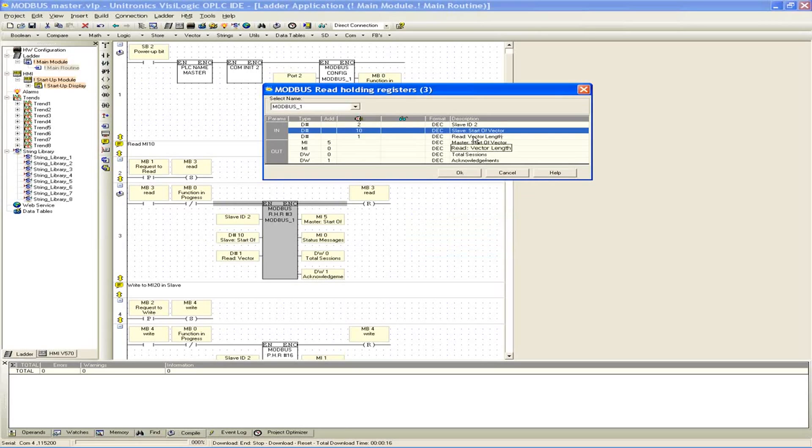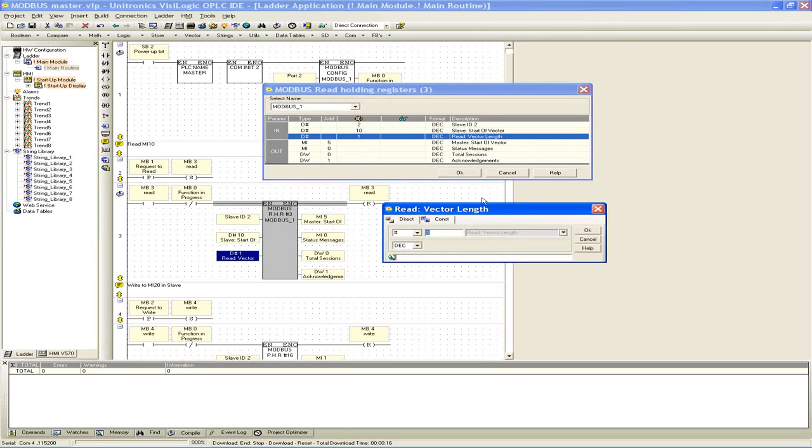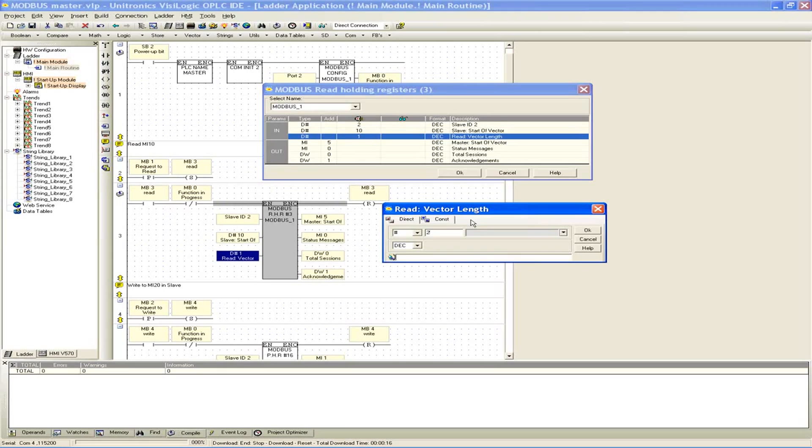Now the read vector length is specified as 1 in this case, so this is really just saying that we're only going to be reading address location 10, which is also equivalent to memory integer 10. If I had made this a 2, it means we're going to read memory address location 10 and 11, which corresponds to memory integer 10 and 11. So you can just read multiple registers if you increase the read vector length.